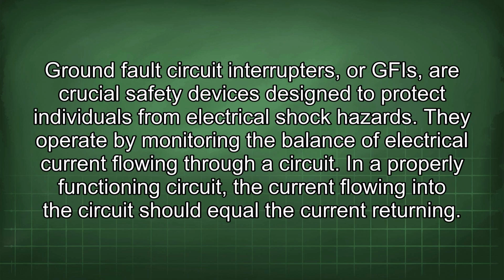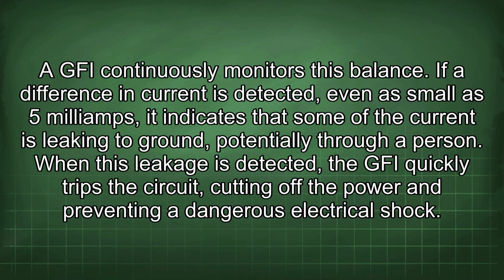Ground fault circuit interrupters, or GFIs, are crucial safety devices designed to protect individuals from electrical shock hazards. They operate by monitoring the balance of electrical current flowing through a circuit. In a properly functioning circuit, the current flowing into the circuit should equal the current returning. A GFI continuously monitors this balance. If a difference in current is detected, even as small as 5 mA, it indicates that some of the current is leaking to ground, potentially through a person.